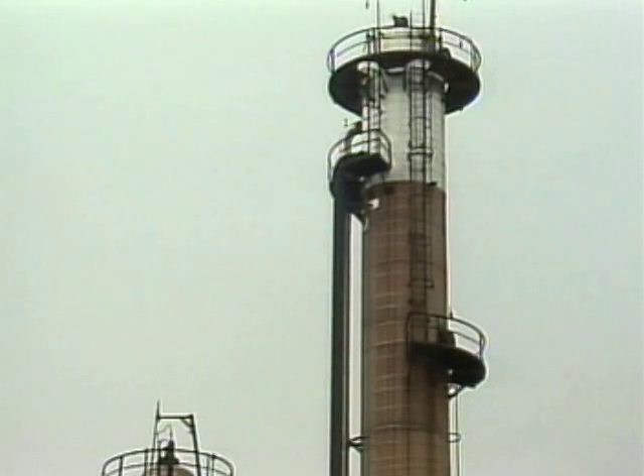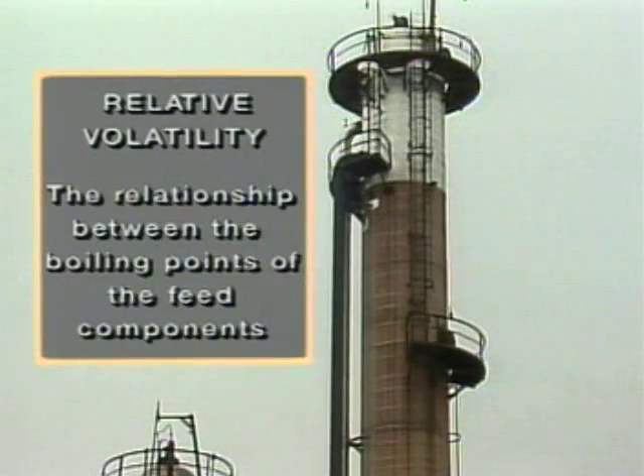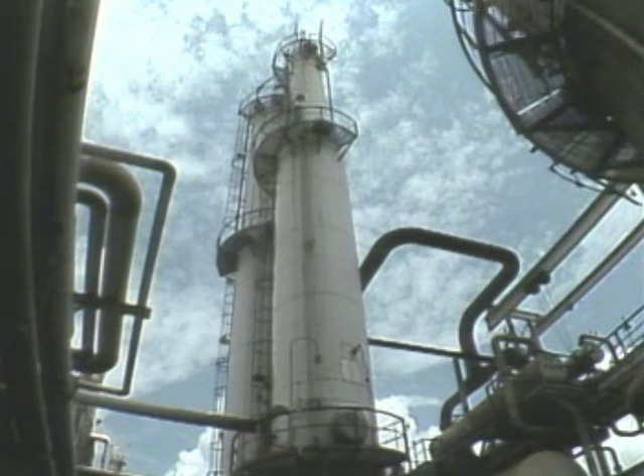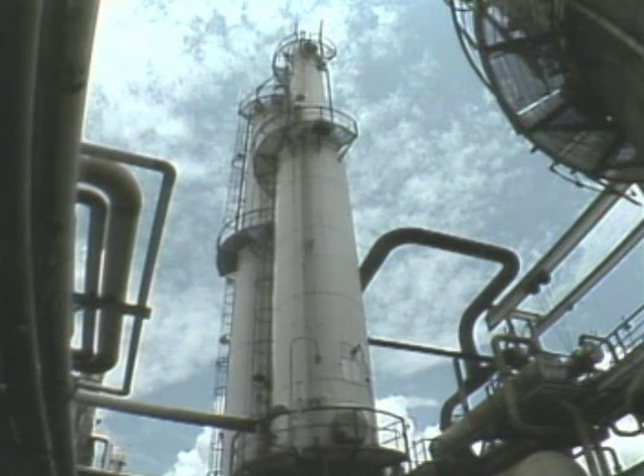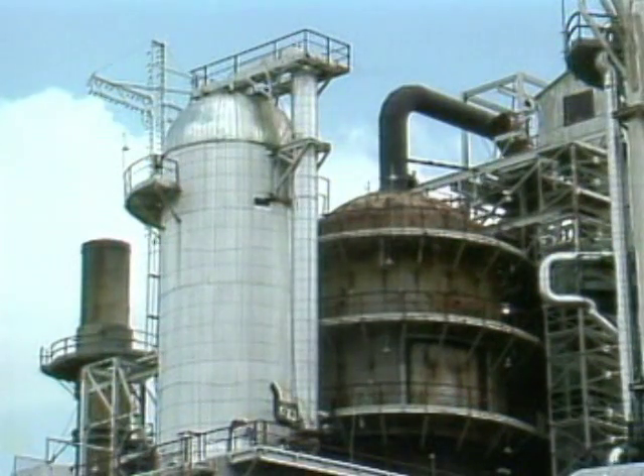The physical dimensions of distillation towers may be different. In general, they are most affected by three main factors: the relative volatility of the feed components, the feed rate, and vapor loading. Relative volatility is the relationship between the boiling points of the feed components. Feed components with a low relative volatility are difficult to separate because their boiling points are close to each other. To effectively separate such components, a tower requires a large number of trays and must therefore be fairly tall.